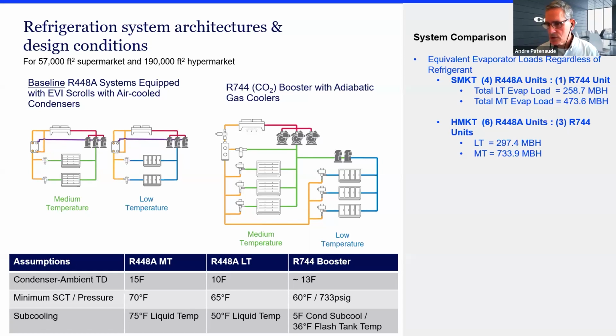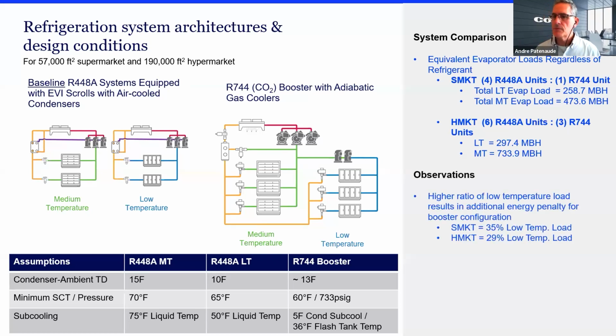And you can see, though, what's interesting is the low temp load is only marginally higher on the hypermarket than it is on the supermarket, but the medium temp loads are much higher. That's typically how they're set up. Now, observations. We really didn't expect it, but what's interesting is the supermarket, the percentage of low temp loads is greater for the supermarket at 35% versus hypermarket, which is lower.